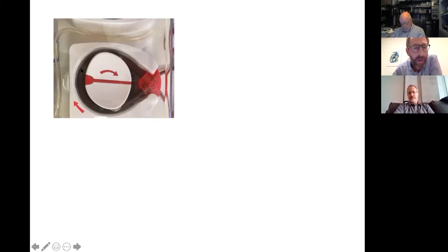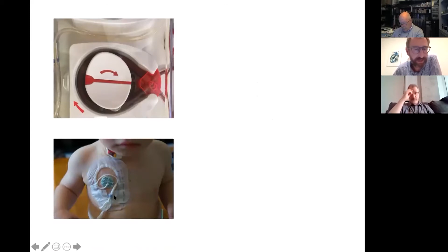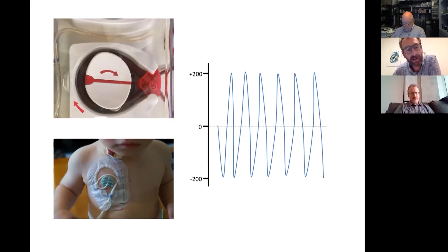This is a typical blood pump, a pump that we have in our adult machines, in our units. And you know that the blood is moved by the action of these two rotors that push the blood in this extracorporeal line. And when we couple this type of pump with this small catheter, this is the risk of having a pressure profile. So the risk is of having high venous pressure, low arterial pressure. This prevents the continuation of our renal replacement therapy, results in several alarms, and is associated with a risk of having clotting in our extracorporeal circuit.